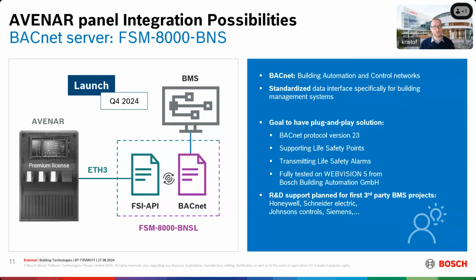We now also launched a BACnet server, and BACnet is working with the same principle. We have the FSI, but now we have a BACnet stack. BACnet stands for Building Automation and Control Networks, and this is now completely standardized. This is actually the data interface specifically for building management systems. And here we do have a plug and play solution.